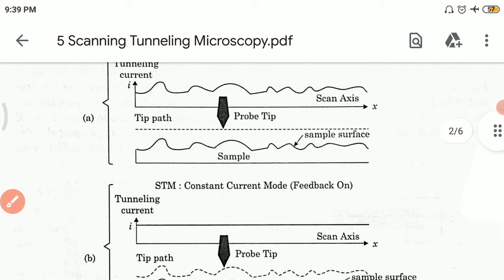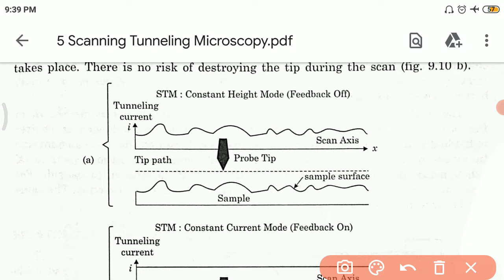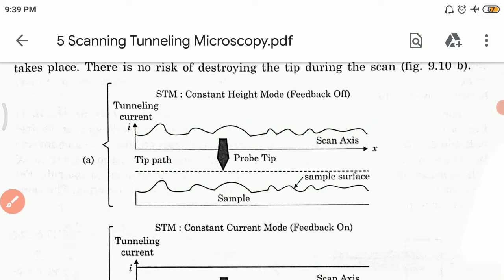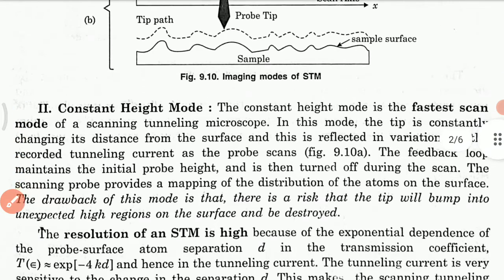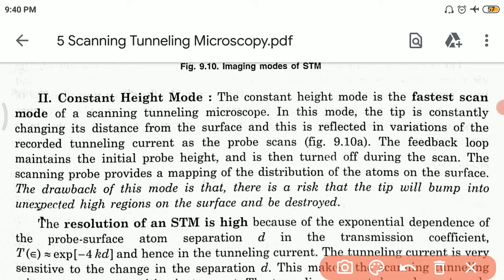Now the upper figure is the constant height mode. You can see here the dotted line is smooth, so the tip is maintained at a constant height and the sample surface is as it was in the second figure. If we measure the tunneling current, then in this case it will vary according to the scan axis. Let us see the second mode which is the constant height mode. Actually it is the fastest scan mode of the scanning tunneling microscope, and in this mode the tip is constantly changing its distance from the surface, and this is reflected in the variation recorded by the tunneling current as the probe scans the area.